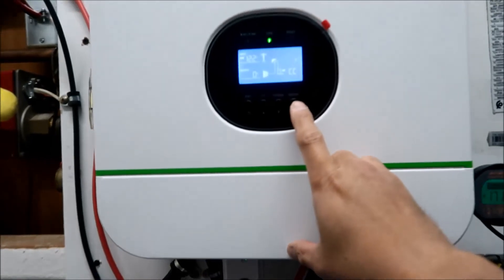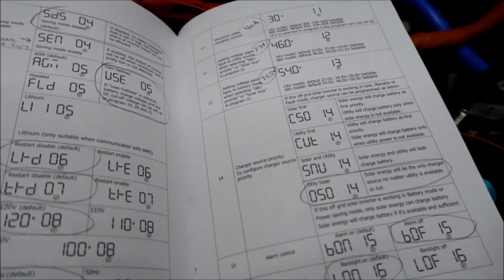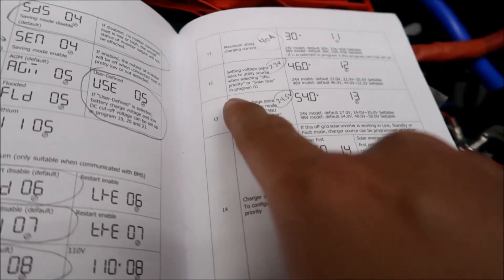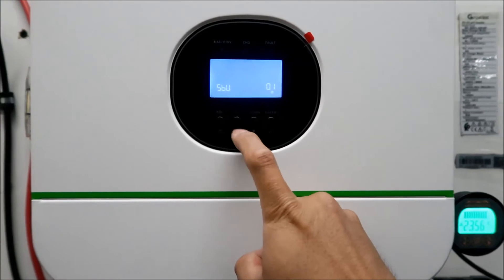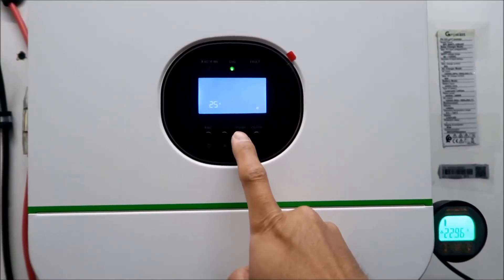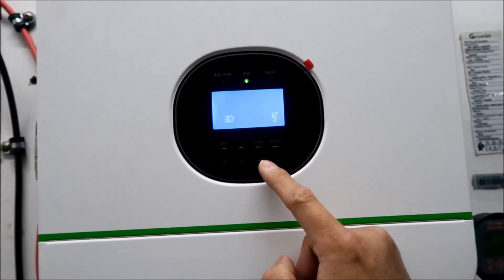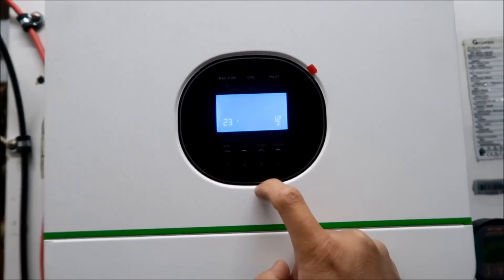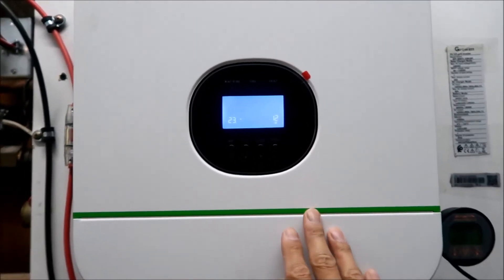I'm going to raise the low voltage cutoff. The setting for voltage back to utility - setting 12 - sending voltage back to utility is at 23 volts right now. I'm going to set it to 23.5 volts. And setting 13, the voltage back to battery mode, is currently 24.5 - I'll raise that to 24.7. I've now set the voltage cutoff a little bit higher.